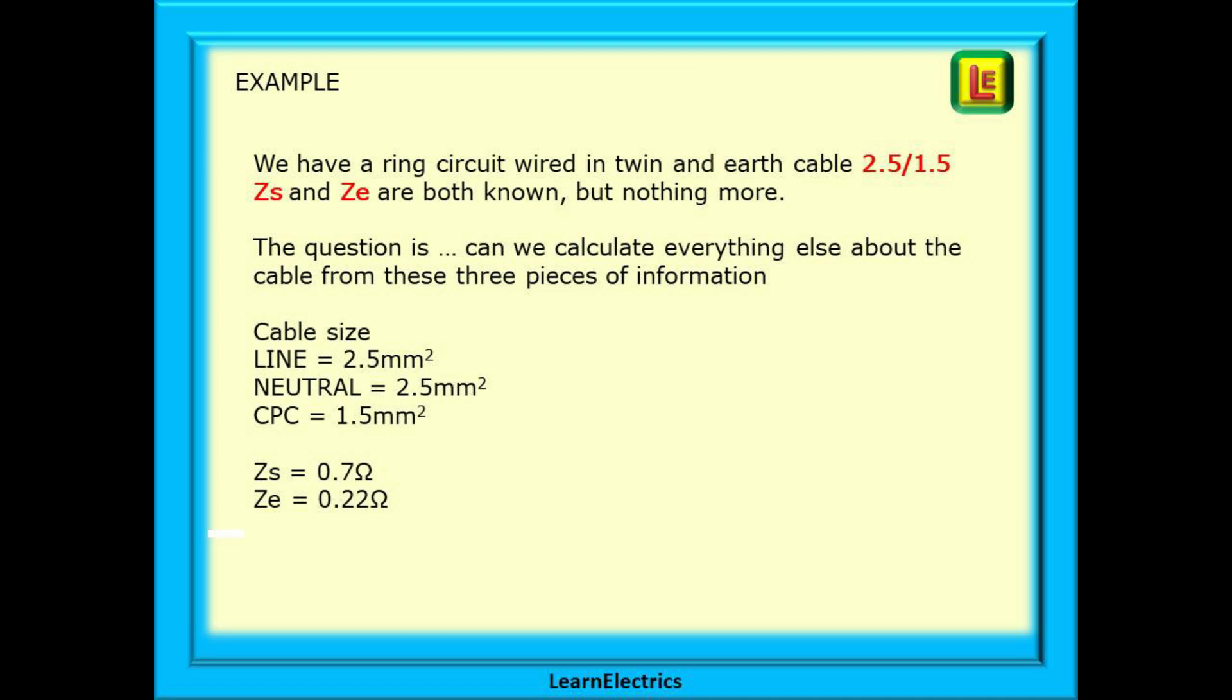We can best show this method with a worked example. We have a ring circuit that is wired in twin and earth cable with a 2.5 mm line and neutral and 1.5 mm CPC or earth. And Zs and Ze are both known but nothing more. The question is, can we calculate everything else about the cable from these three pieces of information?